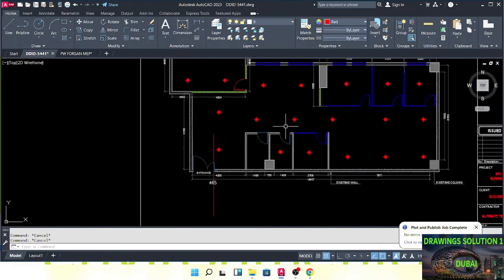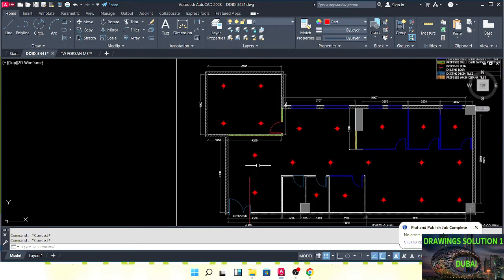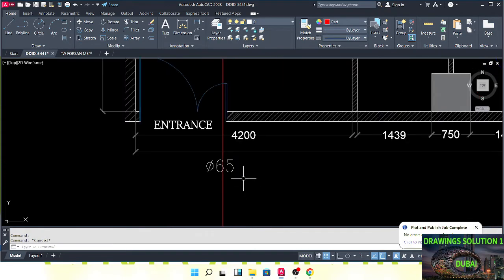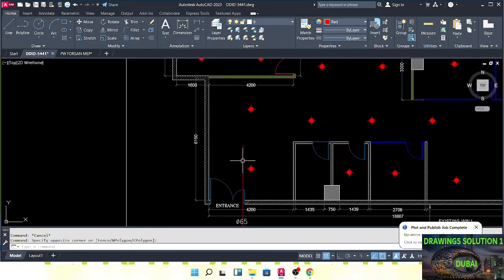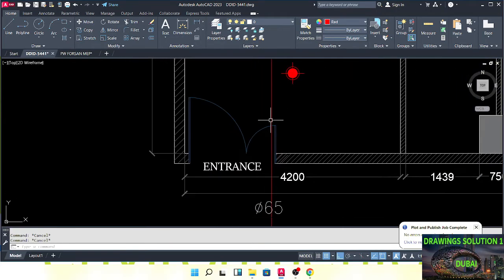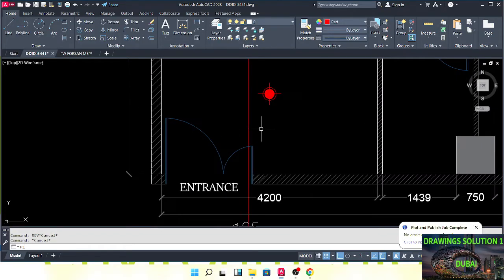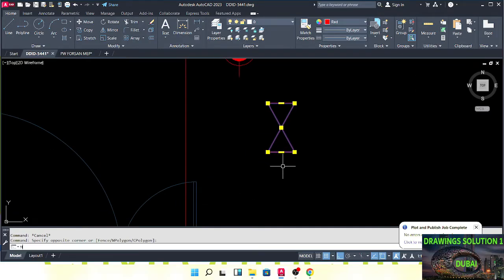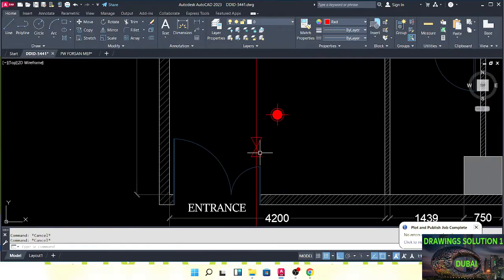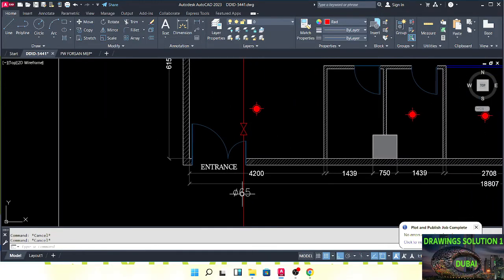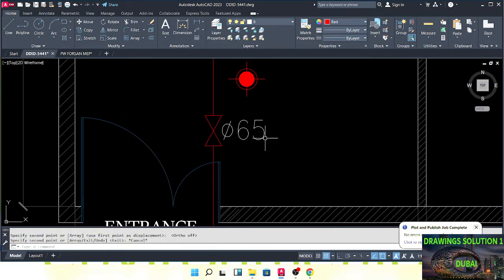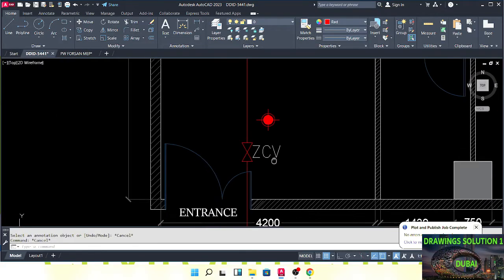This is a bathroom — no need for a sprinkler. But in the pantry we need a sprinkler and I've kept one already. The next process is to make the piping. We have an existing 65mm dia supply given to us already. Here you can make a zone control valve — make a rectangle and give it the name ZCV, which means zone control valve.